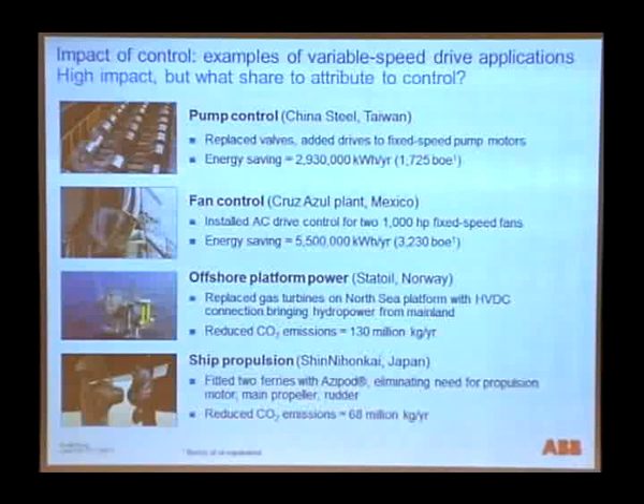Or take ship propulsion, where rather than running the diesel engine through a mechanical shaft to the propeller, you break the loop: do away with the mechanical shaft, run the diesel at its best operating point, then run a cable to an electrical outboard motor that is controllable in a very different way. This gives better maneuverability on a ship, and also anywhere between 8 and 15% energy savings. This is even a double propeller arrangement, counter-rotating, so you gain new degrees of freedom hydrodynamically too.